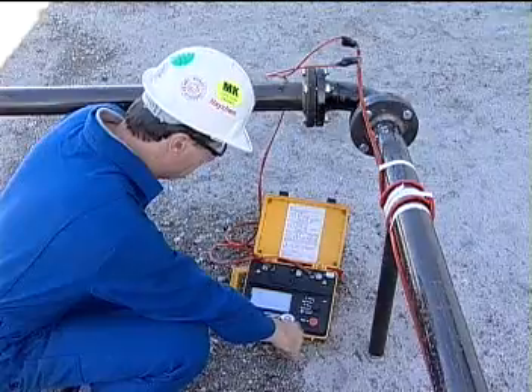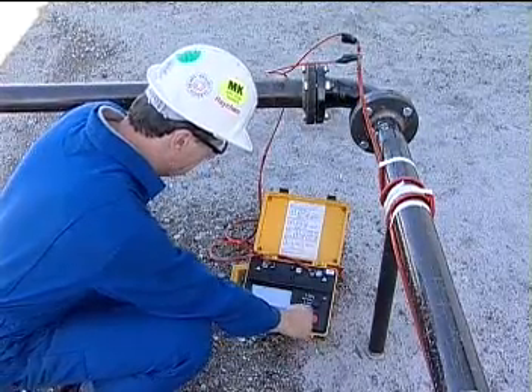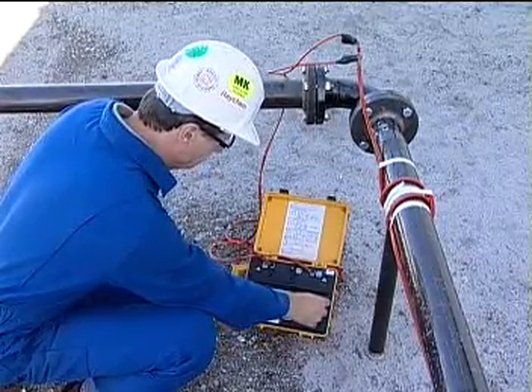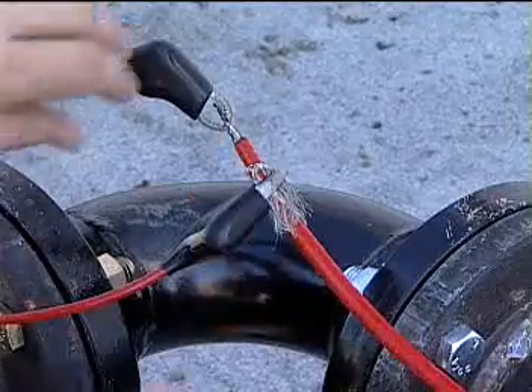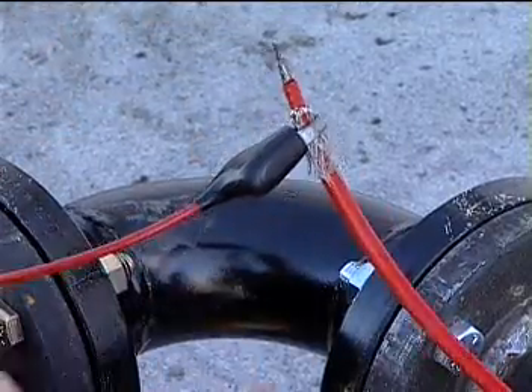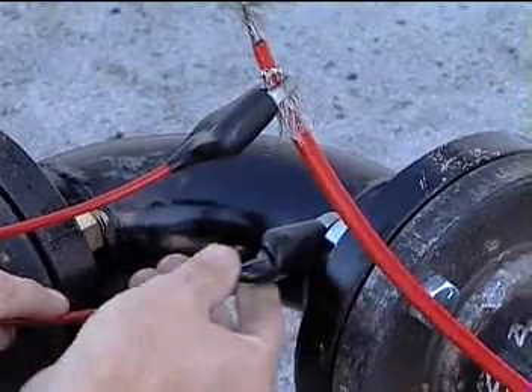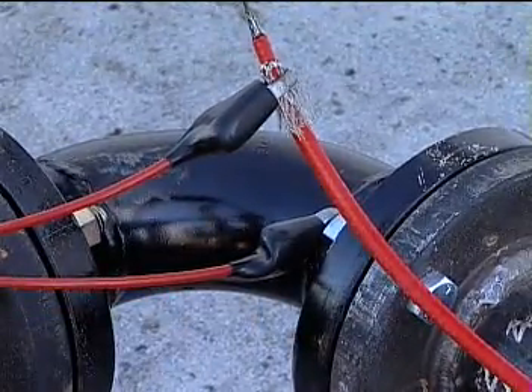First, measure the resistance between the heating cable bus wires and the braid. This test ensures that the inner jacket has not been damaged during installation. Next, measure the resistance between the braid and the metal pipe. This test ensures that the outer jacket has not been damaged.